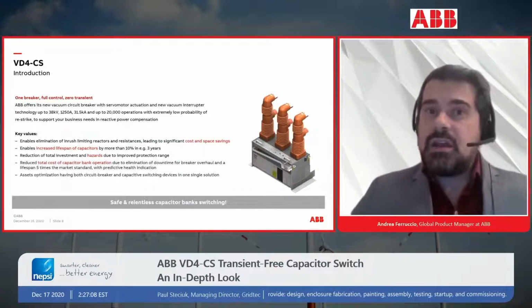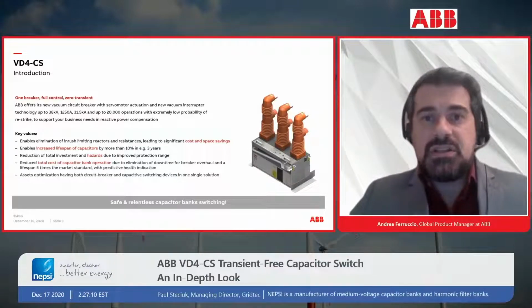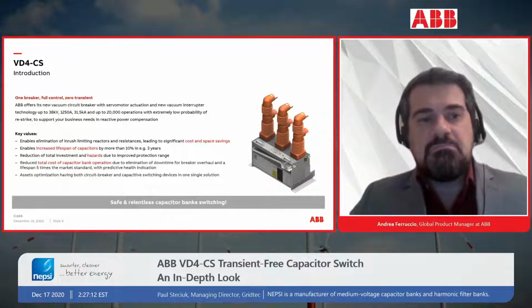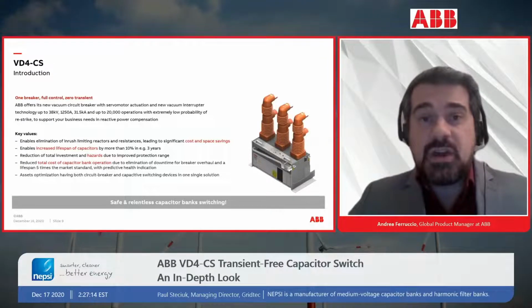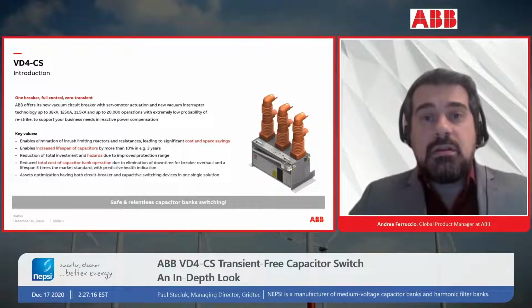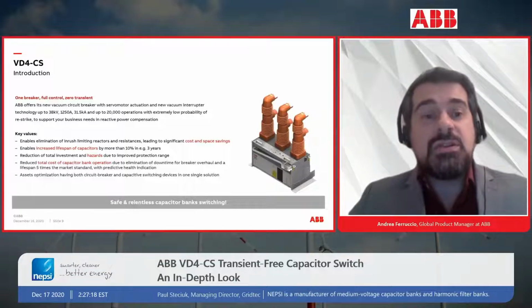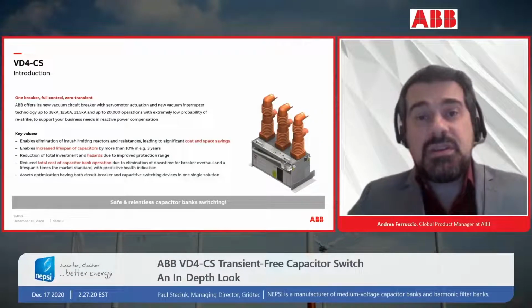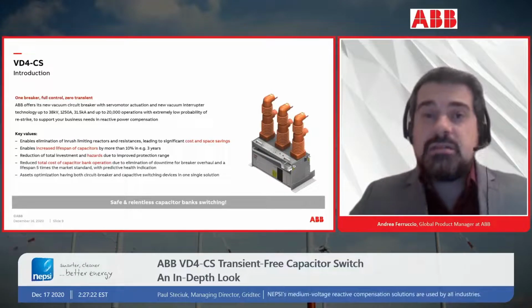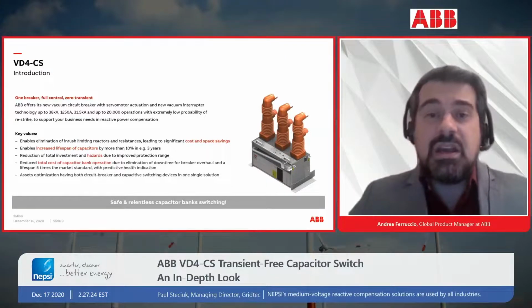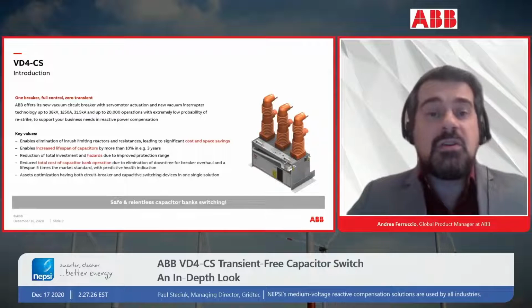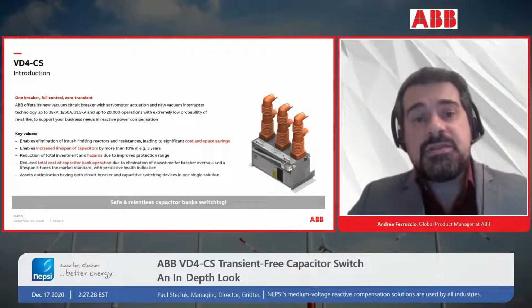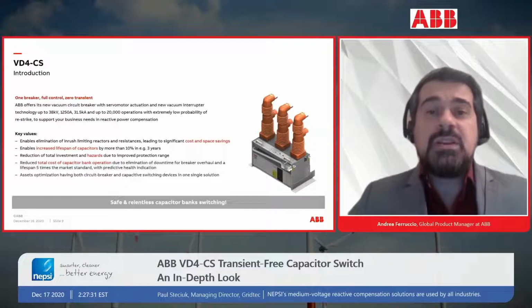Some real technical characteristics of the VD4-CS breaker: a complete circuit breaker based on the innovative solution of the synchronization strategy, completely embedded in the breaker itself, counting on an innovative servo-motor actuation system and new vacuum interrupter technology.